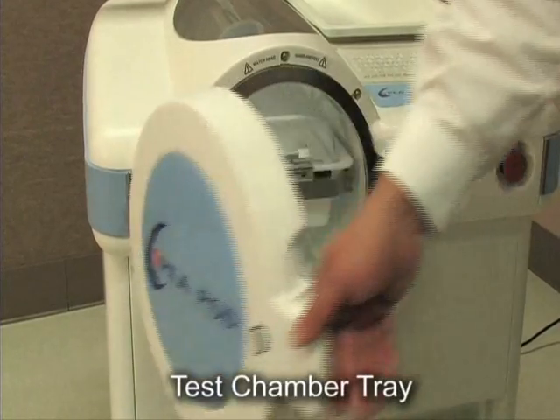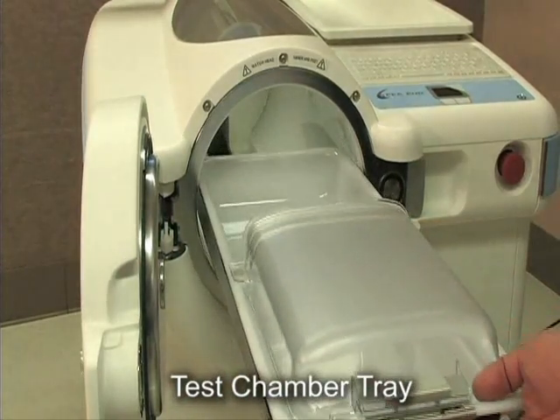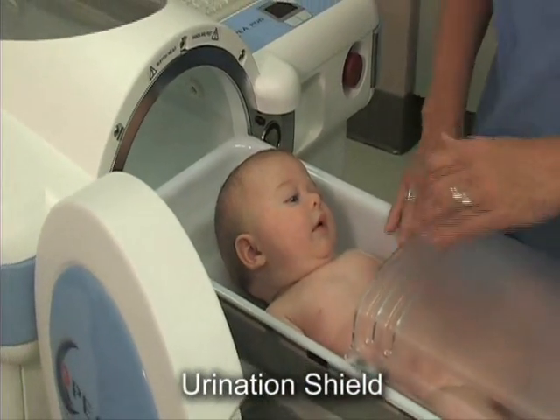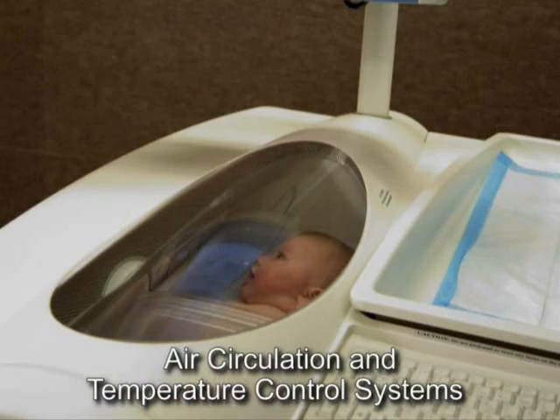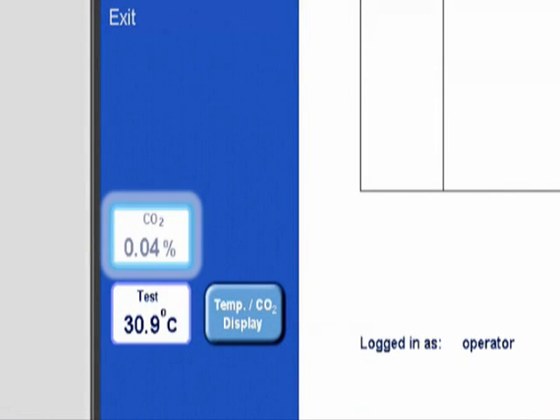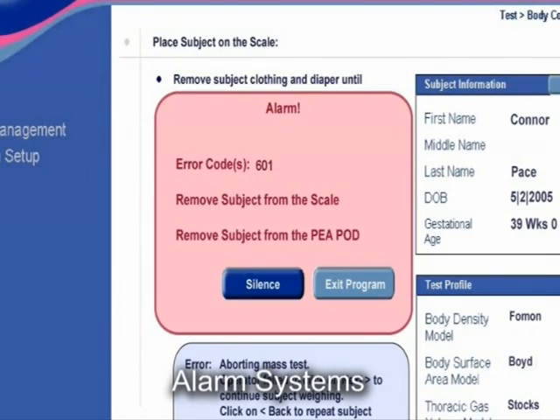The test chamber tray is fully retractable, which allows for easy placement of the infant inside the test chamber. A urination shield is also provided to contain fluids within the test chamber tray. The numerous infant safety and comfort features of the PEA POD's test chamber include air circulation and temperature control systems, which provide a stable thermal microenvironment during testing. Additional safety features include constant temperature and CO2 level monitoring within the test chamber, an emergency off switch, and a sophisticated alarm system.